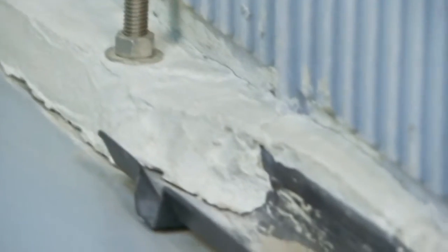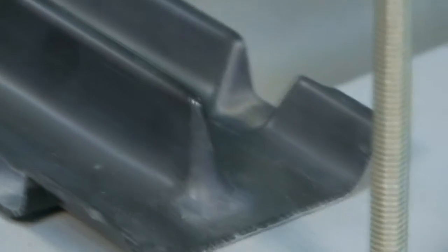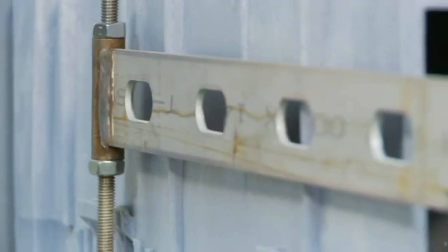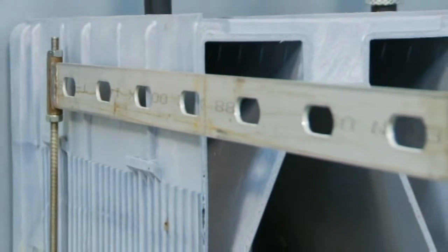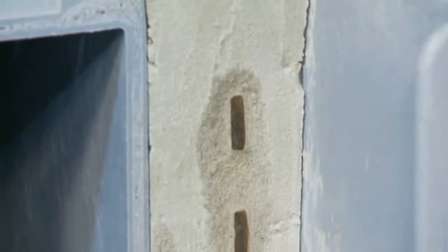This static display also shows the grout retainer strips that are used over the flume to prevent fill grout from entering and filling the flume. Here are the anchor rods that are used over a flume to resist uplift due to the backwash water. After placement, the anchor rods are embedded in the fill grout as seen here.